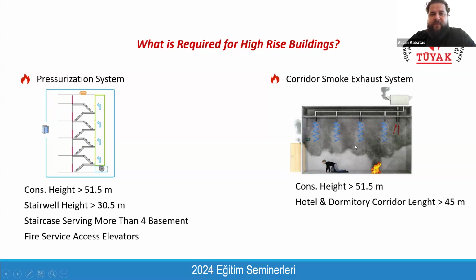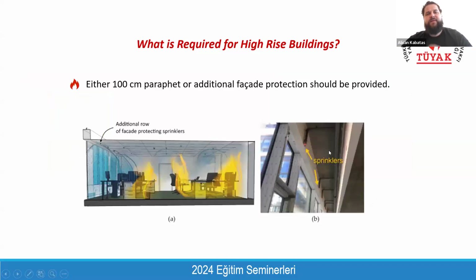Also, we will have some corridor exhaust systems for high-rise buildings with construction height of more than 51.5 meter, and the hotel and dormitory, without looking at the construction or building height, if the corridor length exceeds 45 meter. Either you need to divide the corridors into parts not more than 45 meter, or you should provide a corridor smoke exhaust system. When you have a corridor smoke exhaust system, you need to provide additional shafts for mechanical designer, and it will affect the core design of your buildings. That's why this is also important.